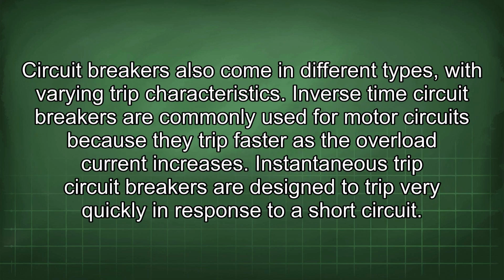Circuit breakers also come in different types with varying trip characteristics. Inverse time circuit breakers are commonly used for motor circuits because they trip faster as the overload current increases. Instantaneous trip circuit breakers are designed to trip very quickly in response to a short circuit.